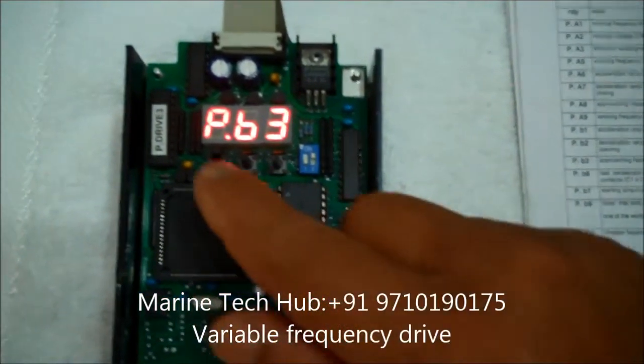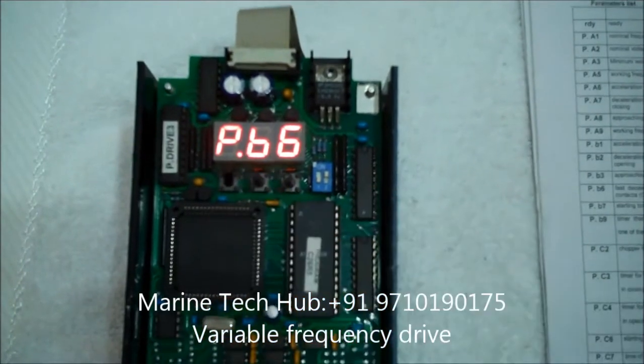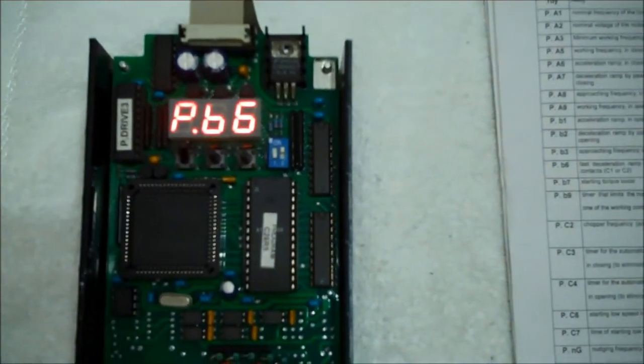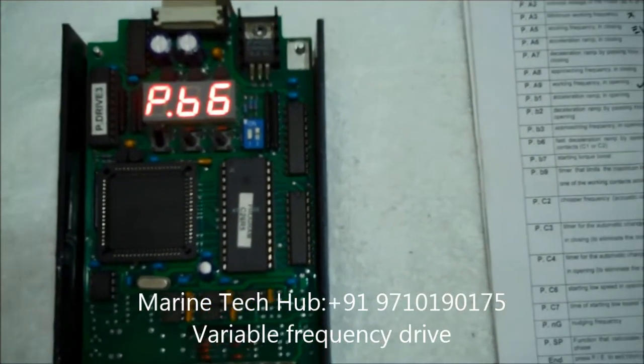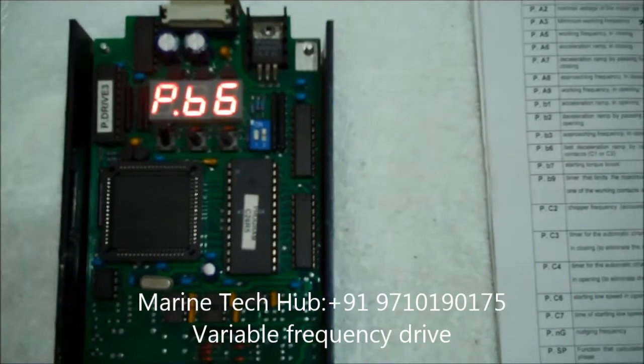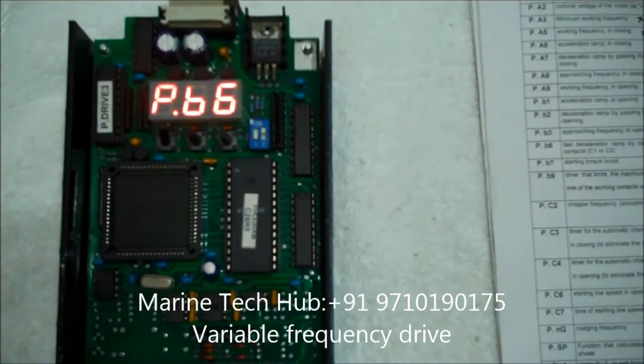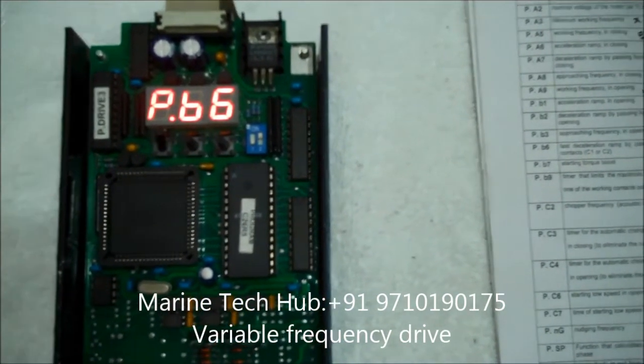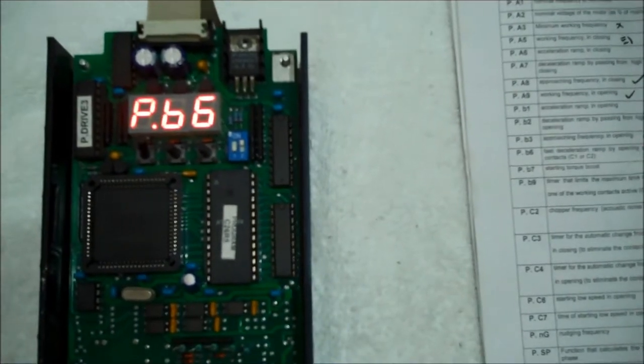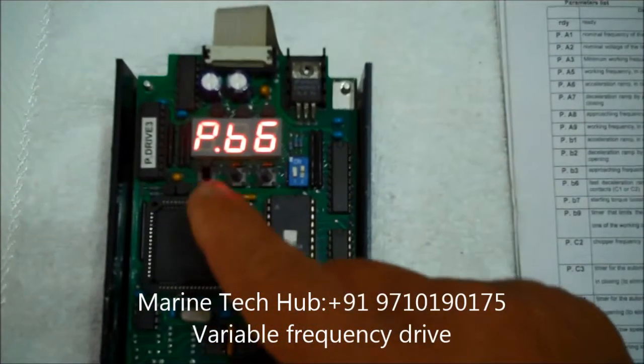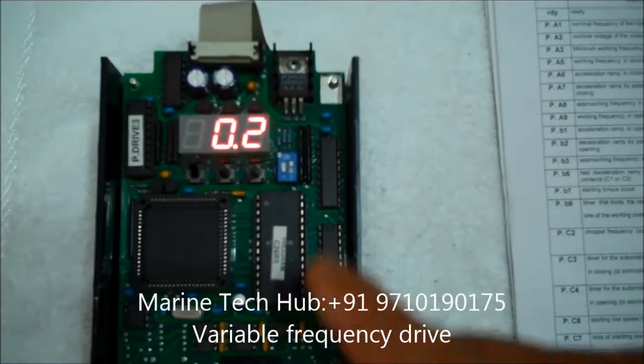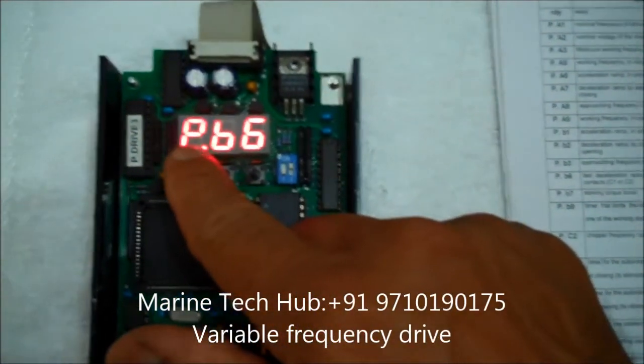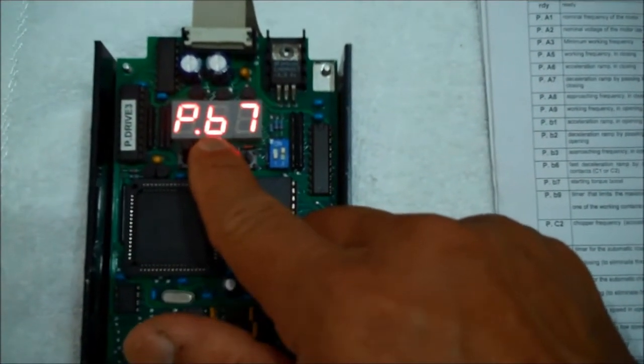Next program will be PB6. PB6 is the fast deceleration ramp by opening one of the working contacts, that is C1 or C2. This is normally in seconds, 0.2 seconds they normally keep it. It is 0.2 seconds. So it is okay.